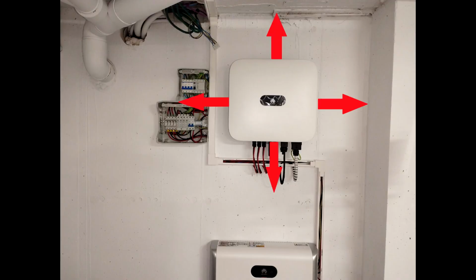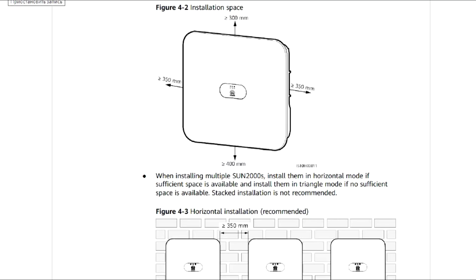It is extremely important to follow the manufacturer's requirements and ensure sufficient clearance around the inverter, especially above it, at least 300 millimeters, and also below and to the sides. The device generates a lot of heat, which must dissipate properly. It must not be installed too close to the ceiling. Otherwise, it will overheat and may fail. For the same reason, the inverter should not be installed in very small rooms without proper ventilation.